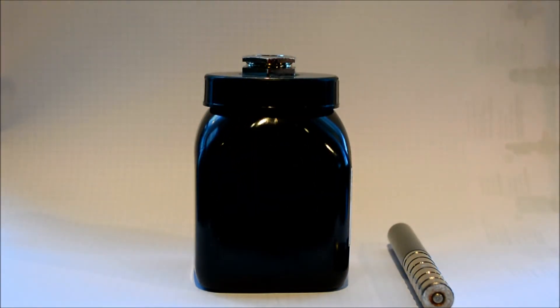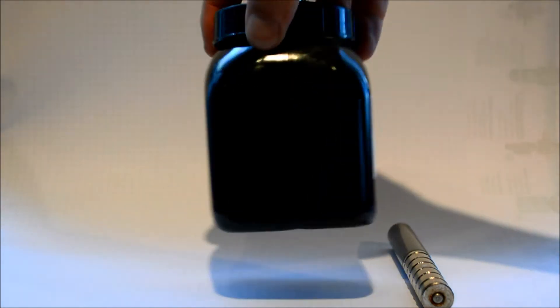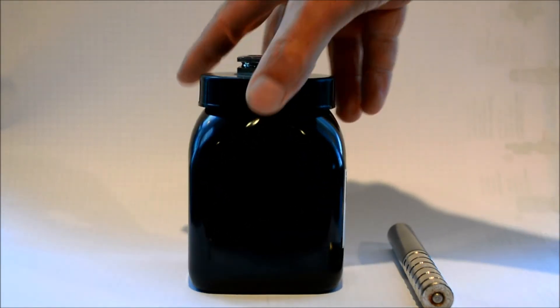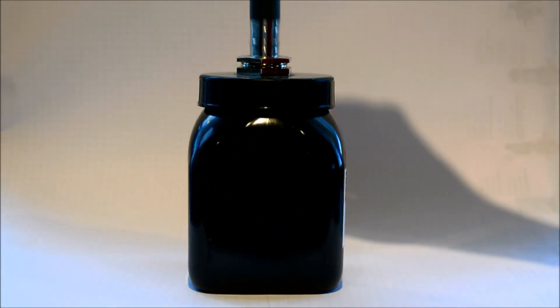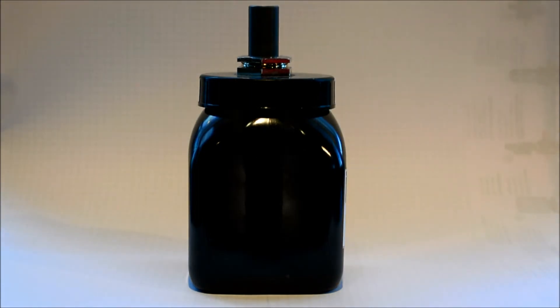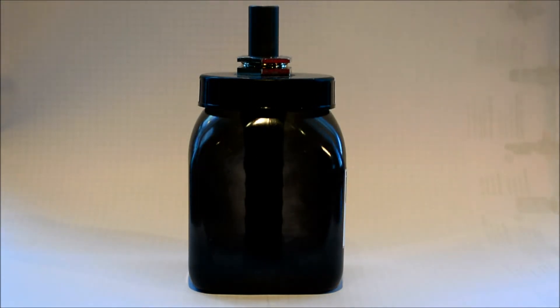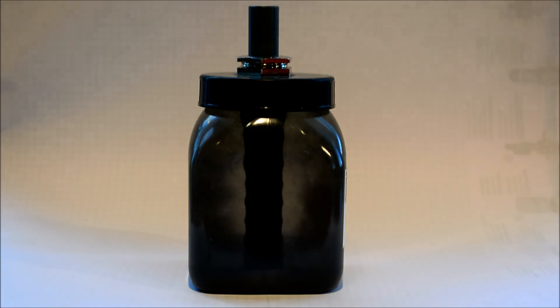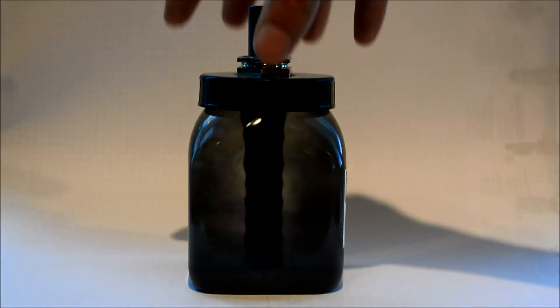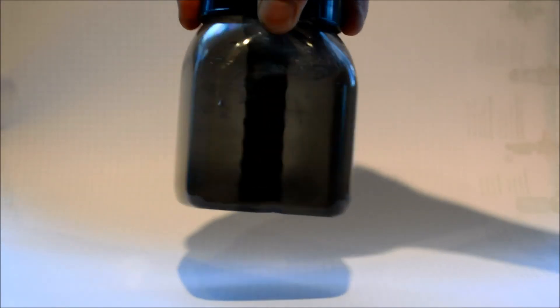So here you can see a dirty water sample from a heating system. We'll shake once more to mimic water flow through the unit. We drop the sample magnet back into the sample bottle, and you can see how quickly that sludge, which is spinning around in the water, gets attracted to that magnet.